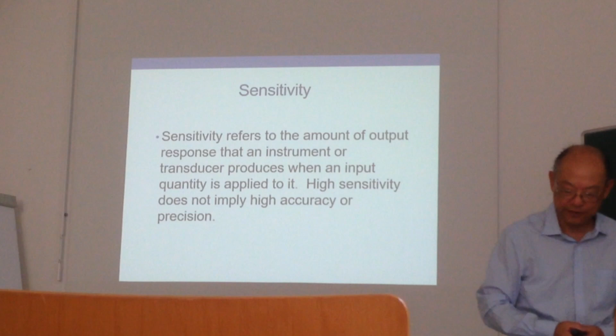The larger the range of measurement — for example, a scale that measures thousands of tons — you'll be lucky to have a resolution of 1 ton. If the whole range is only 1 ton, you can probably get kilogram-level resolution. High sensitivity does not imply high accuracy or precision; it's just how refined the numbers you can get. That's sensitivity.